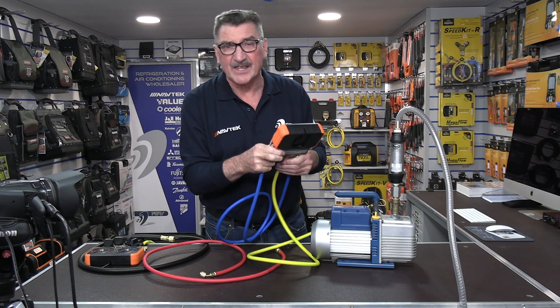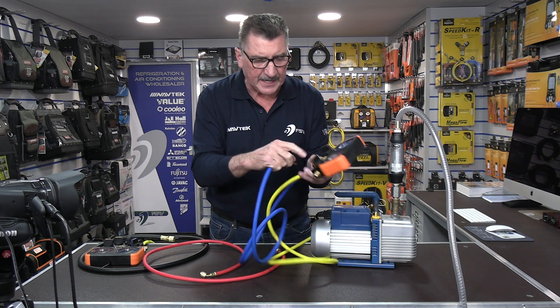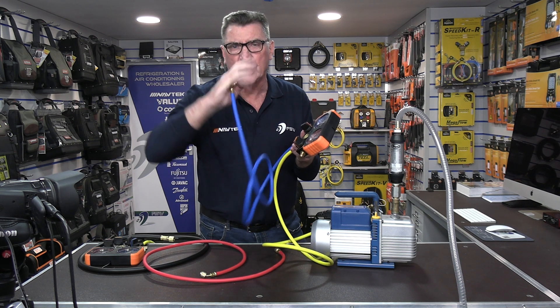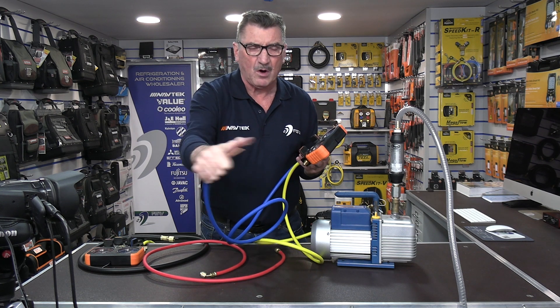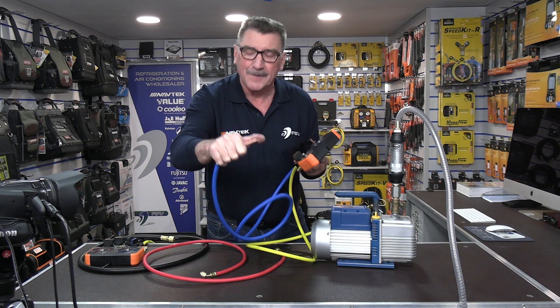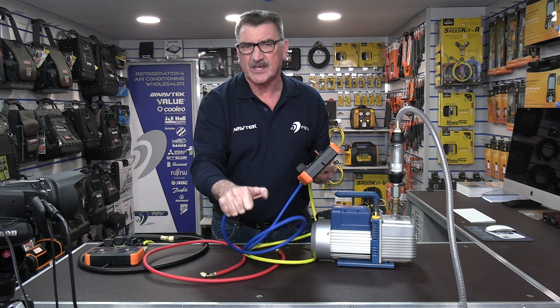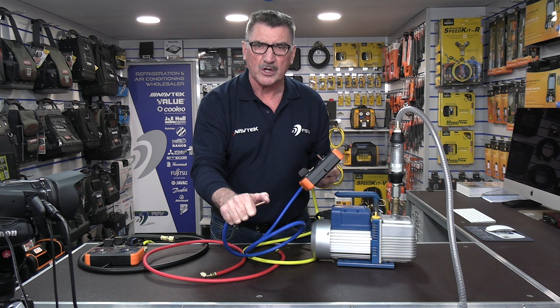It's hard to measure because we're off the scale. There are points on certain manifolds — even running through the manifold, through the valve stem, or on CPS manifolds going through a diaphragm — that can restrict flow even more. That's why we've been lugging around 5 CFM pumps and buying 10 CFM pumps; it makes no difference if you're using quarter hoses.